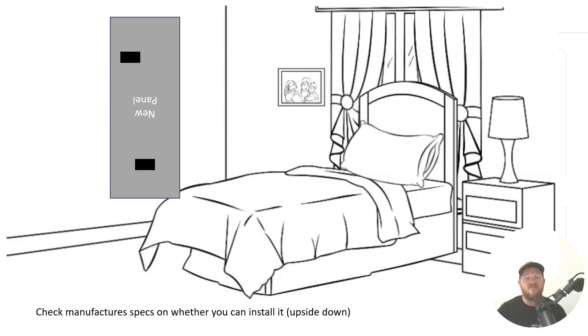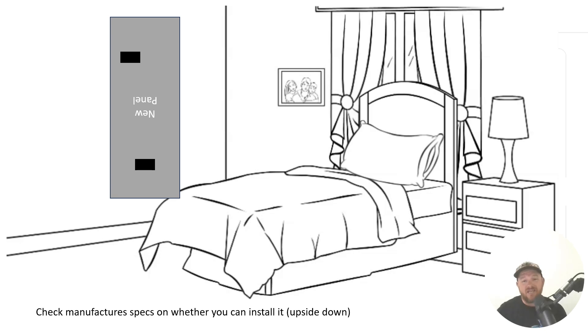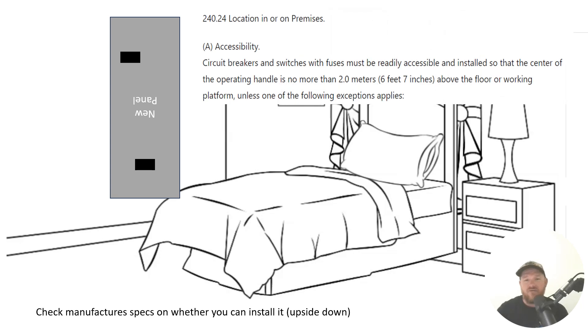As a matter of fact, there are no overcurrent devices that are allowed to be installed above six foot seven unless they're in one of the conditions that are listed below in the code that we're getting ready to cover.